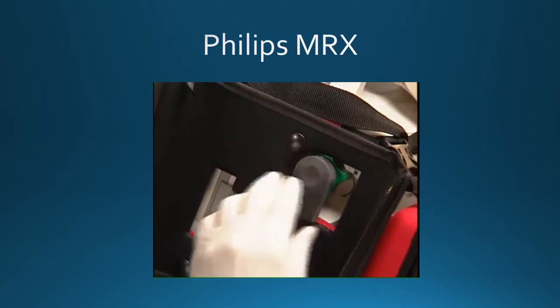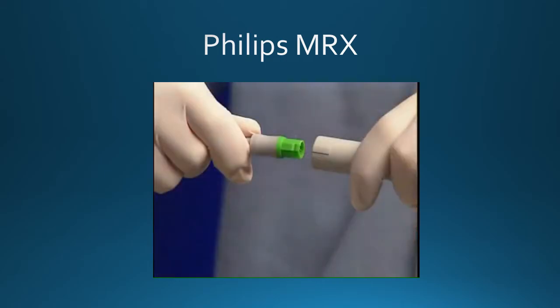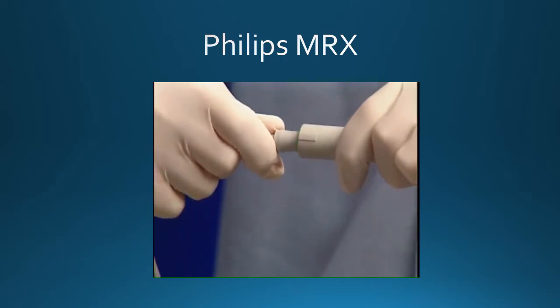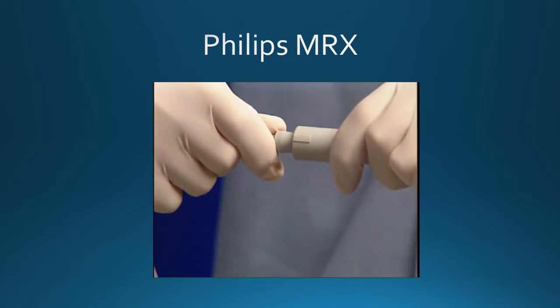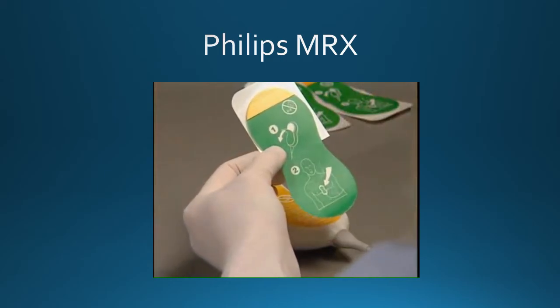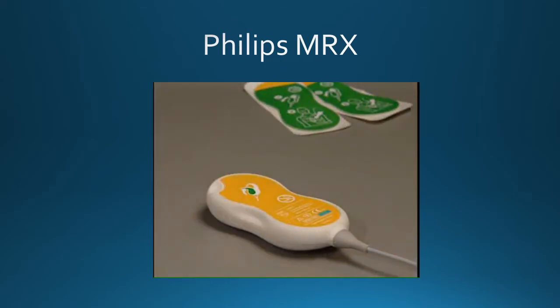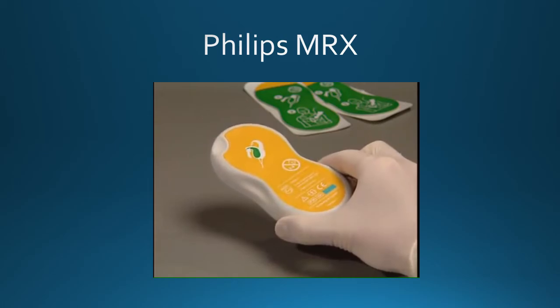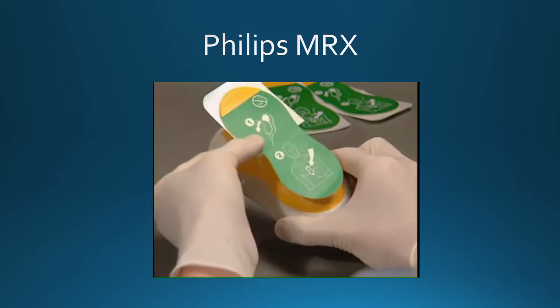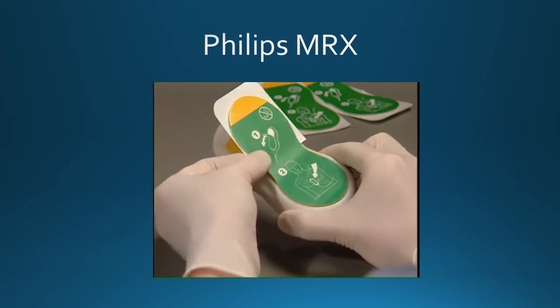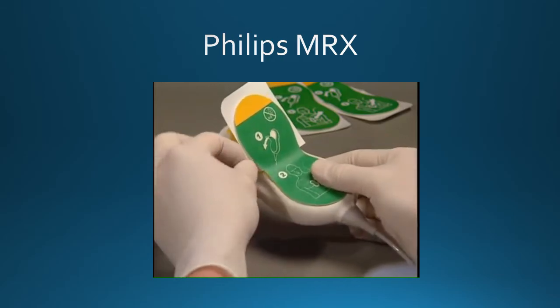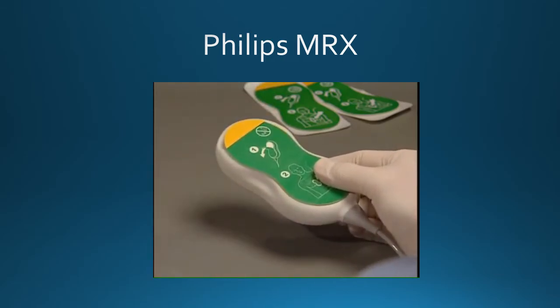The PADS CPR cable is connected to the MRX's therapy port. Align the key marker on the compression sensor cable with the key marker on the receptacle end of the PADS CPR cable. Push until you hear it click into place. Peel the liner from the bottom of the sensor adhesive pad. Align it with the yellow area of the sensor and press it into place. The green surface of the sensor pad indicates that the sensor is prepared for CPR.